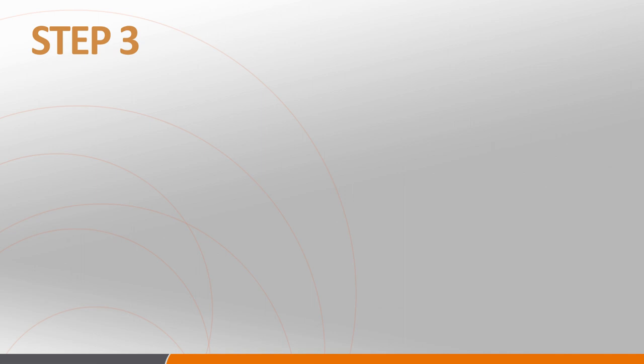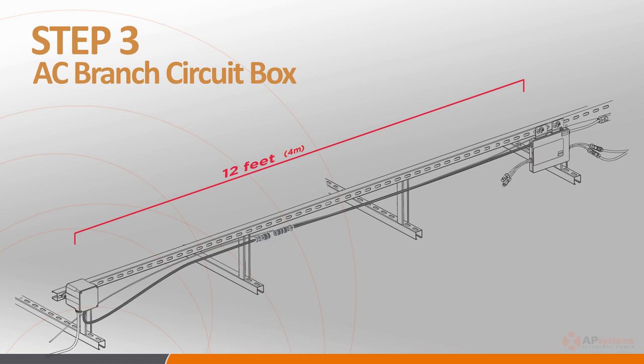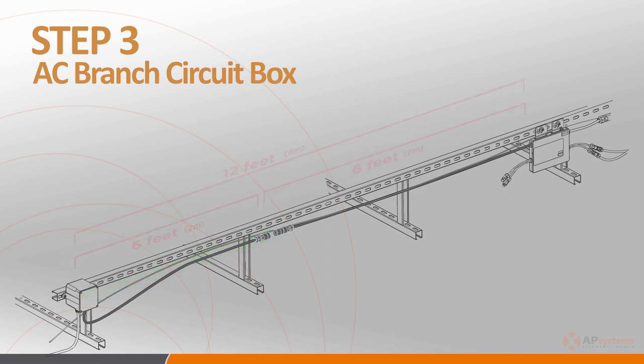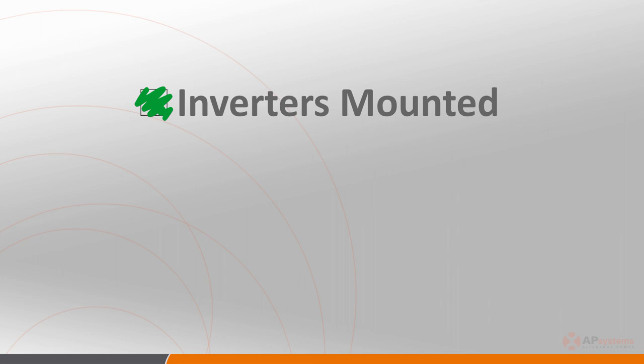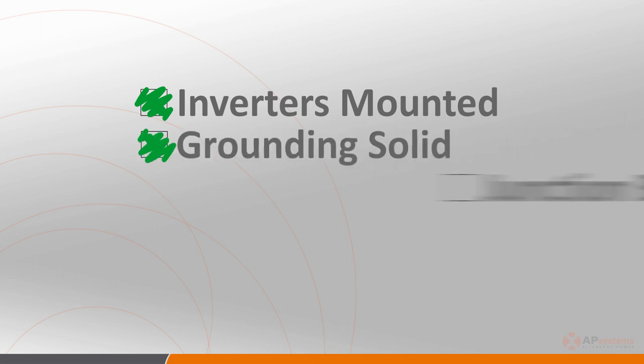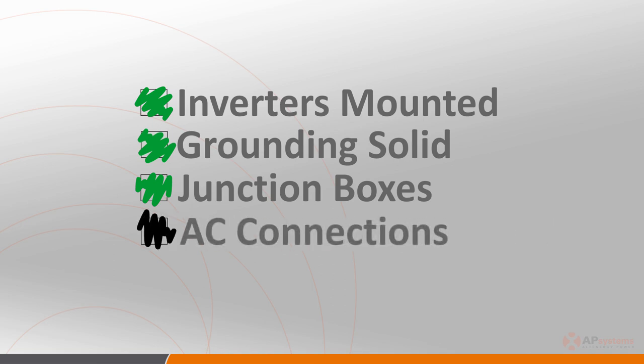Step 3 involves installing the AC branch circuit junction box in a suitable location, as close to the end of a branch of modules as possible. You'll have approximately 12 feet of AC cable to work with: 6 feet of cable associated with the last inverter in the branch, and 6 feet of AC connector cable, sometimes called a whip. Make sure to wire the conductors: L1 is red, L2 is black, and neutral is white. With the inverters mounted on the racking system, the grounding all sorted out, and junction boxes installed in the appropriate locations, it's time to connect the microinverters together on the AC side.